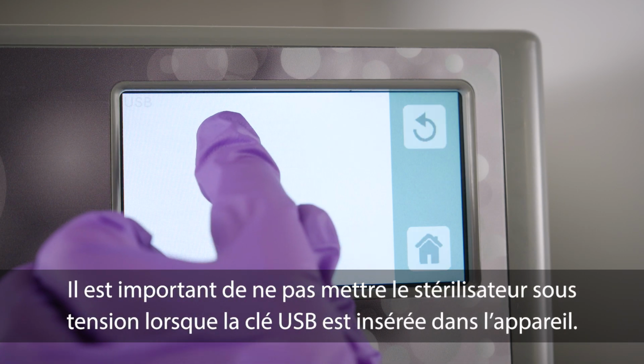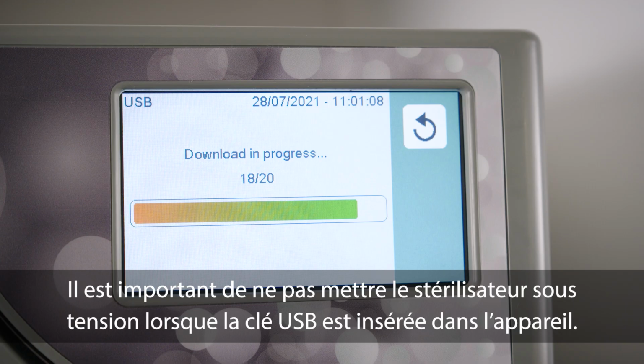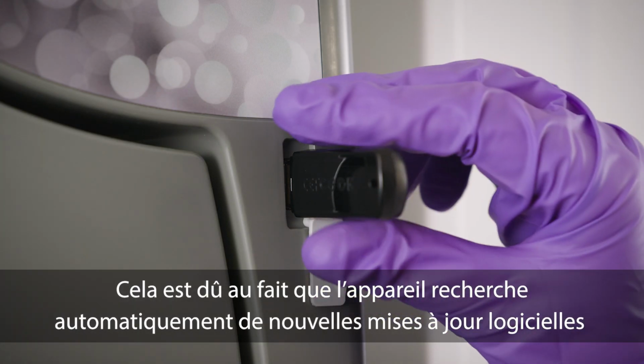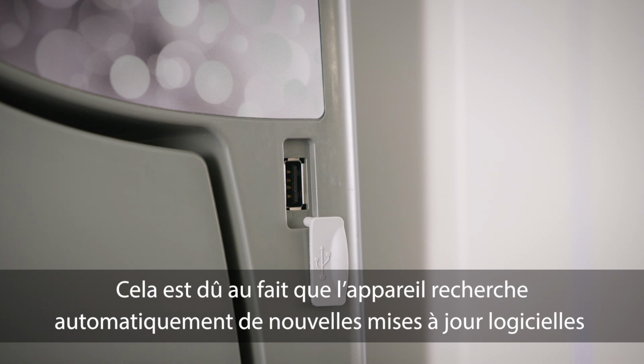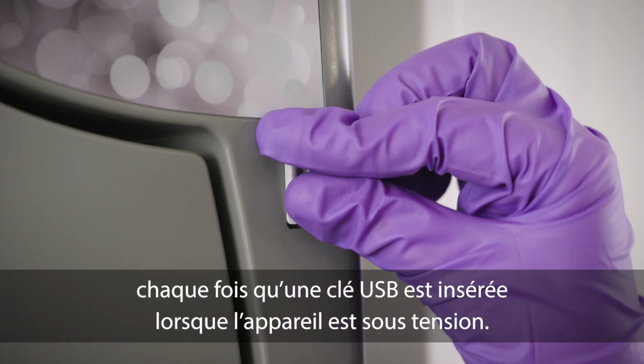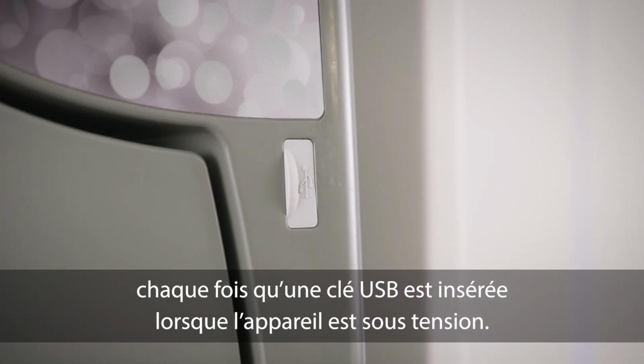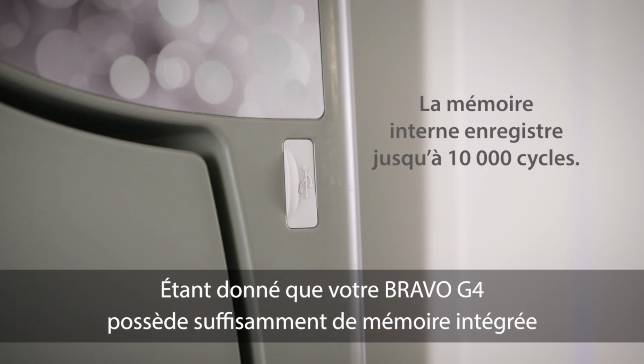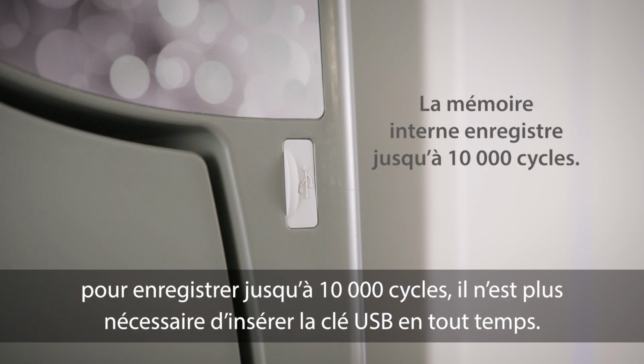It is important to remember not to turn on your sterilizer while the USB is inserted into the machine. This is because the unit automatically looks for new software updates anytime a USB is inserted when the machine is turned on. Since your Bravo G4 has enough built-in memory to save up to 10,000 cycles, having the USB inserted at all times is no longer necessary.